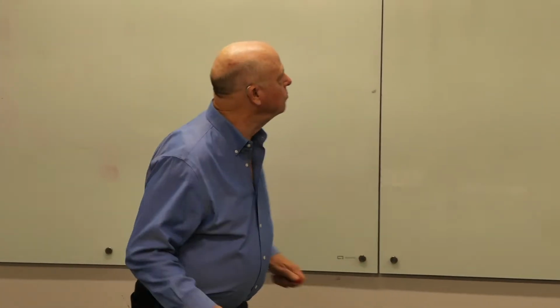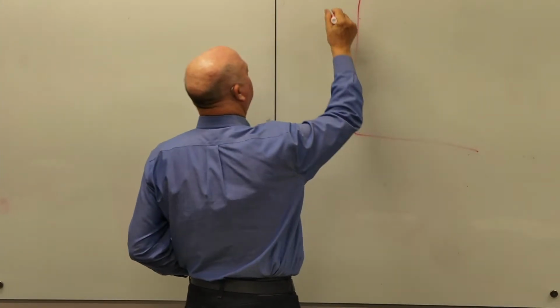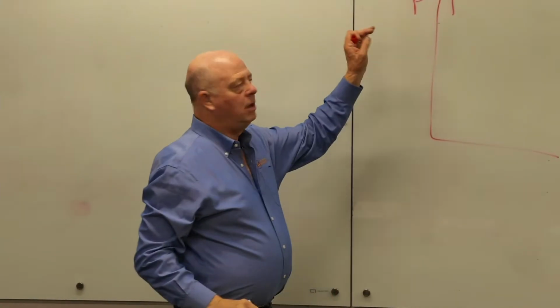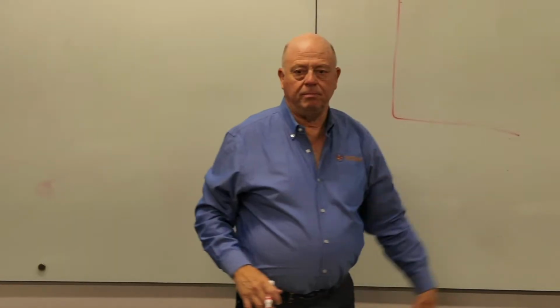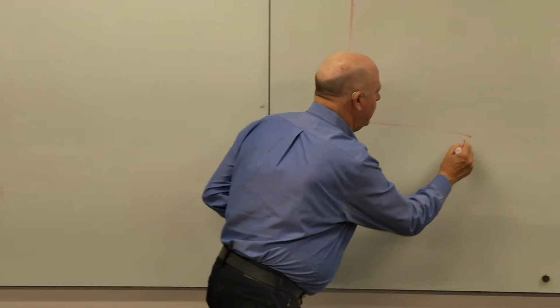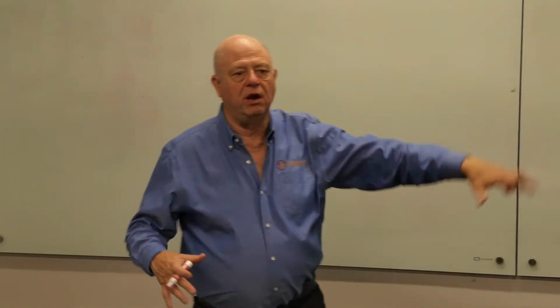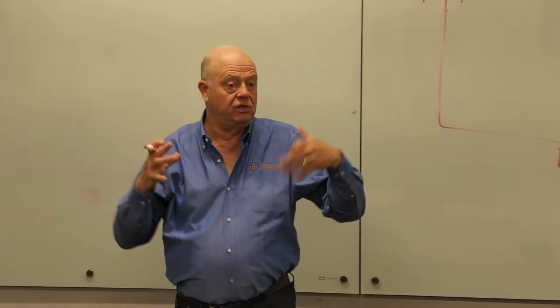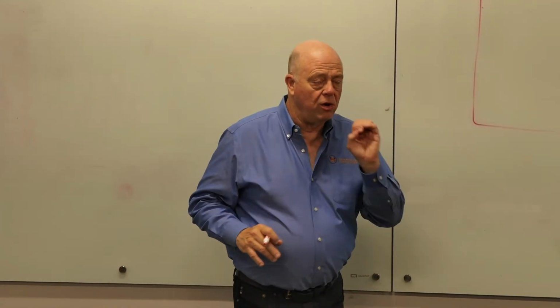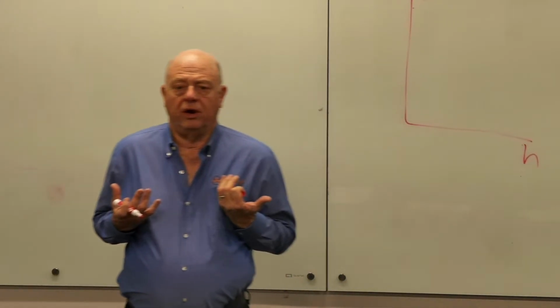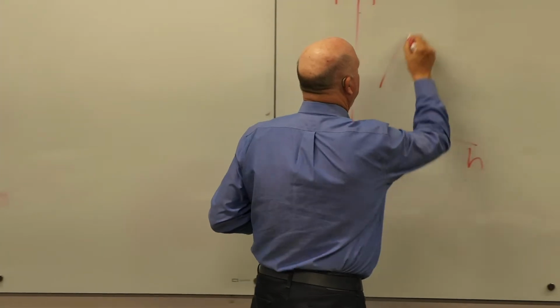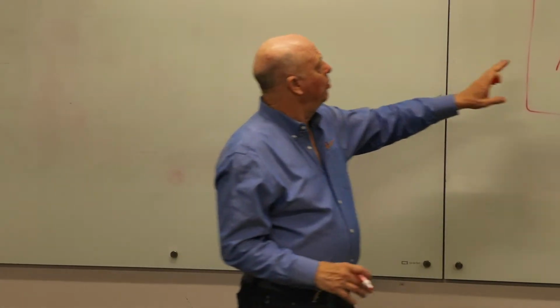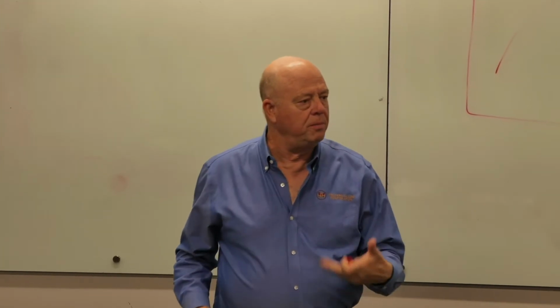So we're going to rehash a couple of fundamentals. And you guys have learned, right, to just interrupt me if there's something you want to talk about that gets said. Okay, you all remember what a pH diagram looks like, right? And you remember that pressure and temperature for a homogeneous refrigerant are the same. For a given pressure, there's a given temperature. And the amount of energy that's in the refrigerant at any given time, enthalpy, is a function of its pressure and/or temperature, and also its state, which for the sake of air conditioning, we don't care about solid, we just care about liquid and gas. And we've got this dome thing, and the dome thing represents when the refrigerant is partially liquid and partially gas.